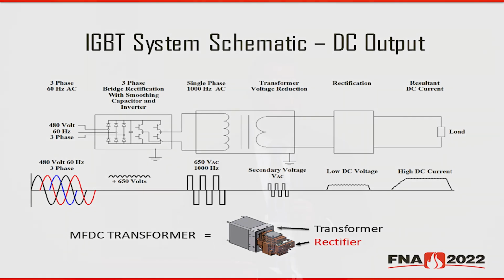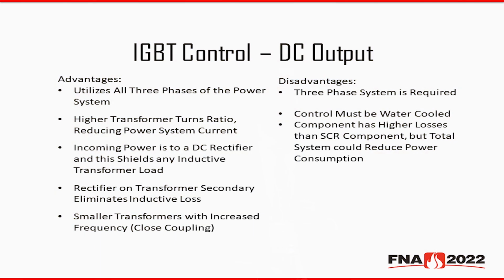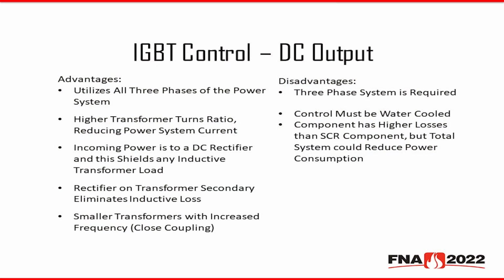Another question? In the schematic that you showed, you mentioned that SCRs and IGBTs were used, sort of like the initial rectification and inverting stages. I believe you said SCRs there, and then IGBTs later. Why, it's my understanding that certain powers are interchangeable, so why the selection of one, why not IGBTs throughout? So IGBTs are more expensive, and they're better used for the high frequency transmission of power versus the rectification. They're not able to turn on and produce that square wave as fast. So the SCRs are just used at the beginning of the component to rectify to that DC bus. We have actually looked at using MOSFETs for the secondary circuit, but MOSFETs just don't have the capacity to do what the IGBTs are able to do.